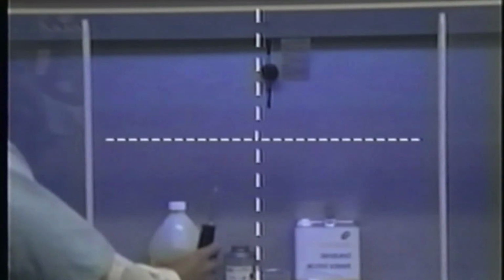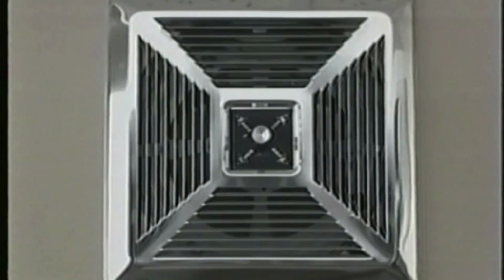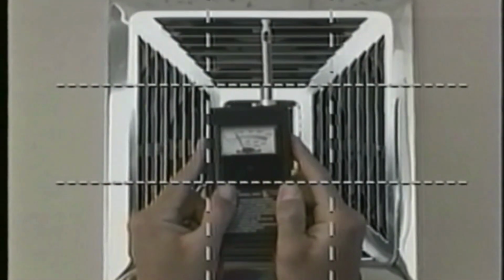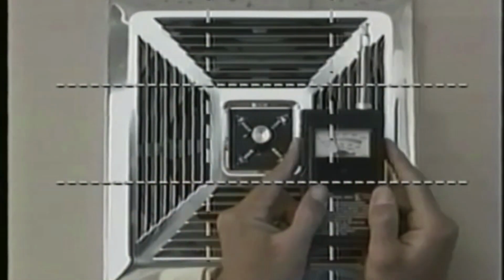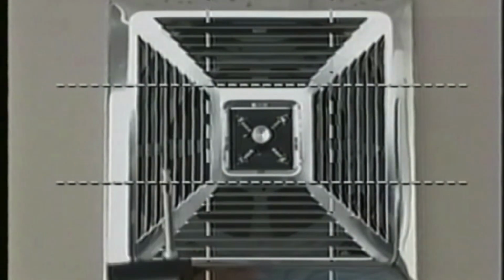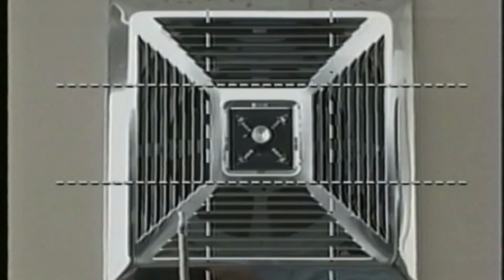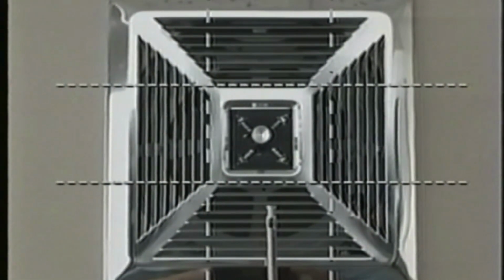The measuring procedures for spray booths are very similar to the fume hood procedures. The 9850 is capable of reading air velocities at grills, louvers, and duct openings. The recommended method for taking a reading is to divide the opening or grill equally in at least 8 square sections. Readings should be taken at the center of each section, approximately 4 inches away from the opening or grill. These readings are used to determine the average air velocity.